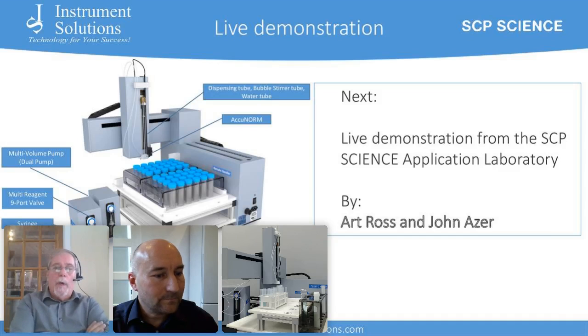Yes, it's a very good question, and this is all about the control of the amount of washing that one does on the outside of the probe and on the inside of the probe. As a chemist, we typically have learned in our schooling that you need 3 times the volume or you rinse 3 times. So if we pick up 1 ml of sample and we do a 9 ml dilution, we've rinsed the inside of the tube 9 times. So we need to rinse the outside of the probe, and typically we control the depth that the probe goes into, so it's only going in a few millimeters, and normally our default value is that we're using 3 mLs to rinse the outside of the probe. So the final answer to the question is we don't see that contamination when we look at the worst case scenario of what's required in terms of the dilution factors that you're using.